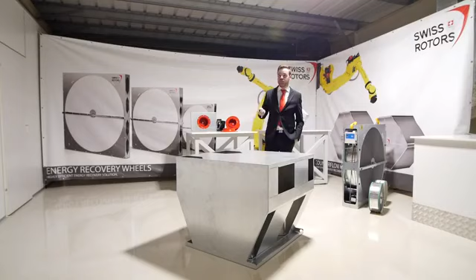So up to 64,000 meters cubed an hour, whilst retaining 78% wet efficiency at a pressure drop of around 250 pascals. Now 250 pascals I know is quite high, but typically we would expect the selection points on this unit between around 120 pascals to around 220 pascals. So you can figure that we're going to be getting airflows above sort of 55,000 meters cubed an hour when we're at that level of airflow and efficiency.